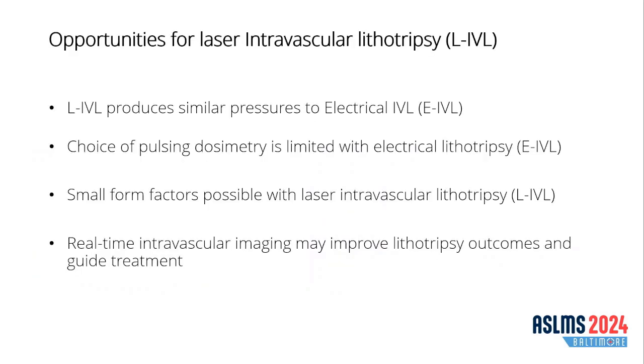So a summary of this part of the talk would be that LIVL, which is what we call laser IVL, produces similar pressures compared to electrical IVL. The choice of pulses is much more limited in the electrical approach. You can only go one shot at a time, versus the laser approach where that limitation doesn't exist, in addition to it being a smaller form factor and having the capability of being incorporated with real-time imaging.